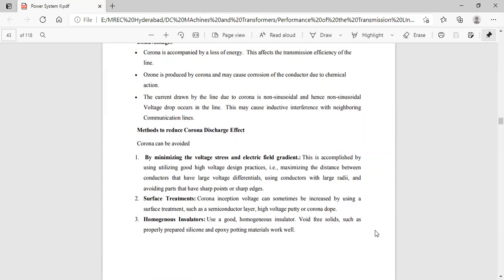Now we will discuss the methods to reduce the corona discharge effect. Corona can be avoided, first, by minimizing the voltage stress and electric field gradient. This is the first step to reduce the corona discharge effect in the transmission line. This is accomplished by utilizing good high voltage design practices, that is, maximizing the distance between the conductors, having large voltage differentials, using conductors with large radii, and avoiding parts that have sharp points or sharp edges. The second point is surface treatments. Corona inception voltage can sometimes be increased by using a surface treatment, such as a semiconductor layer, high voltage putty, or corona dope.